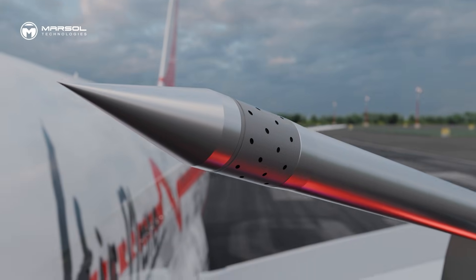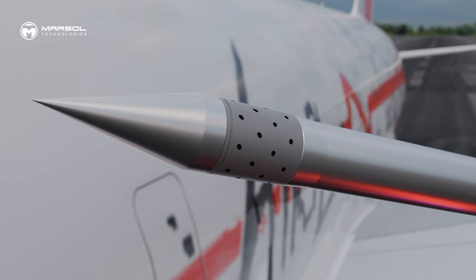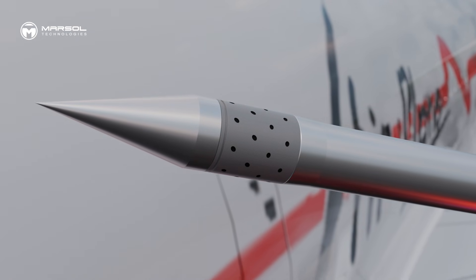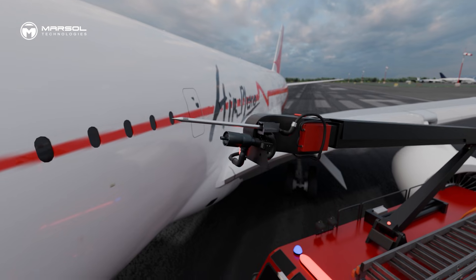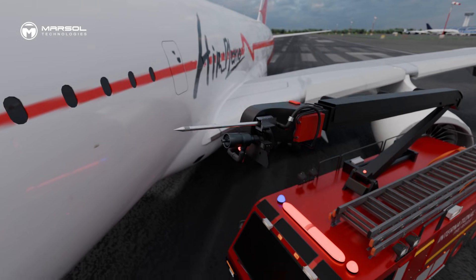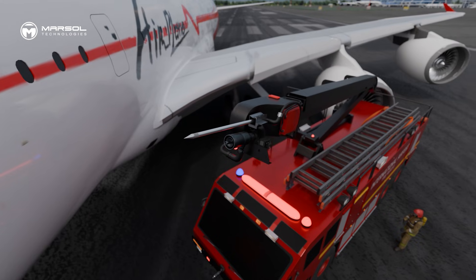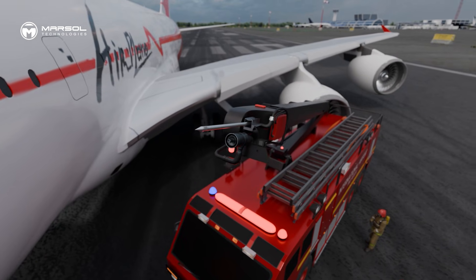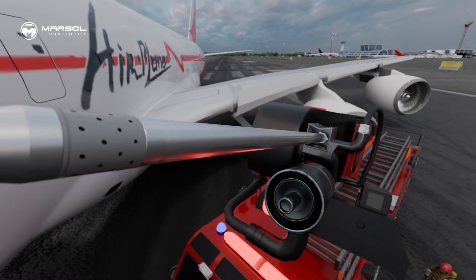This nozzle delivers over 295 gallons per minute at 175 PSI and is factory tested up to 450 PSI, ensuring performance under extreme conditions. Constructed with 316 stainless steel and Kevlar rotors, offering both durability and maneuverability for frontline response.